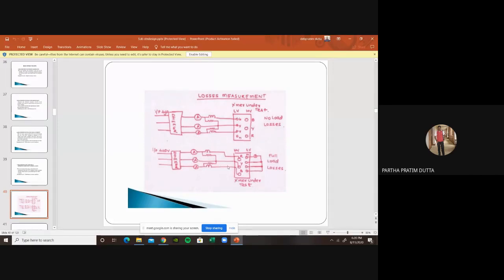In case of full load loss, while we are doing the full load loss test, we usually apply the voltage to the HV side, keeping all the connections of the LV side short circuited. We put the voltage to the HV side in such a manner that the full load current of the HV side can be attained. The moment this full load is attained, we measure it through an ammeter, we stop that voltage, and the test is done. In that manner, we usually do the full load loss and no load loss tests.